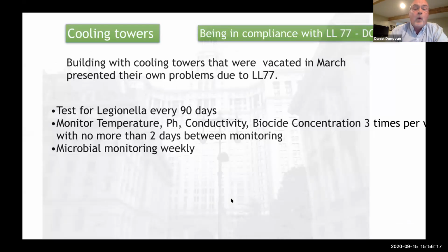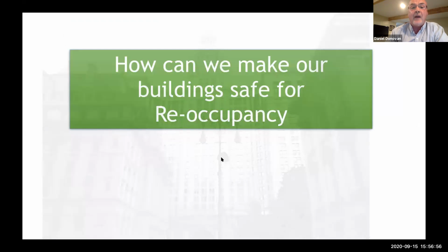Cooling towers, another one. We had a few buildings that were shut down and we needed to move some staff around because we're very short. But keep in mind, if you shut a building down with a cooling tower, you've got to start up again with a mechanical cleaning. So to mitigate that, we would have someone go there every day and just circulate the water within the cooling tower. Then we would monitor temperature, pH, conductivity, biocide concentration, and microbial monitoring weekly. And that's to get our buildings back to where we wanted them to be.